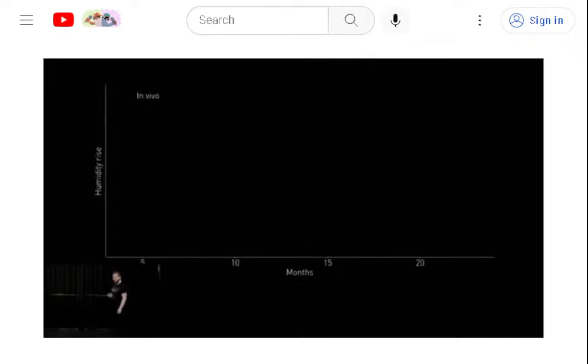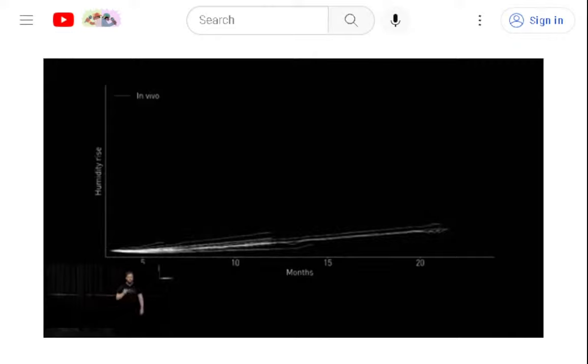Historically, one of our greatest challenges has been the battle against moisture ingress into our implants, so we continuously monitor the internal humidity to watch for abnormal rise. Here, in white, you can see some internal humidity data from implants in some of our animals for the duration of over 1 year. As you can see, our internal humidity sensing is so sensitive, it can even detect the very small and slow humidity rise just from diffusion through our implant materials.